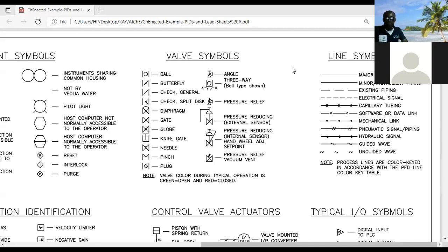And once it bursts, you know what is going to follow the gas, which is fire. So the PRV, the pressure relief valve, is there to relieve the excess pressure if it goes beyond what it is meant for. Before you mount your PRV on those lines, you need to size it against the MAWP, the maximum allowable working pressure of that line.